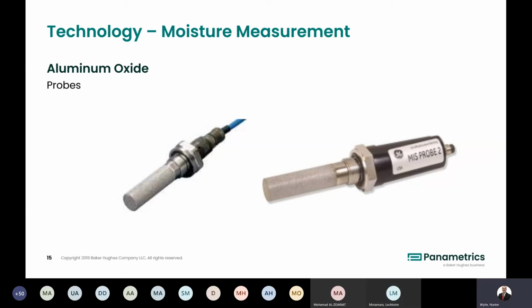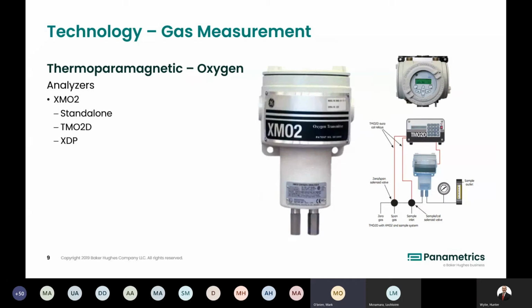Certainly. I think this one we'll throw over towards Mark O'Brien: how do the background gas curves interact with the XMO2? Yeah, I was just typing a response there already. Different background gases interact differently with the XMO2. We find once the XMO2 is calibrated accurately with the specific gas that it's being put into service with, then it has minimal effect on the transmitter itself, as long as we say that the unit is suitable for that application. So once the customer checks with us and says, here's my gas composition, will your transmitter measure with this background gas? And once it's agreed that it will, and we do that calibration here, then there should be no issue in the field with that background gas.